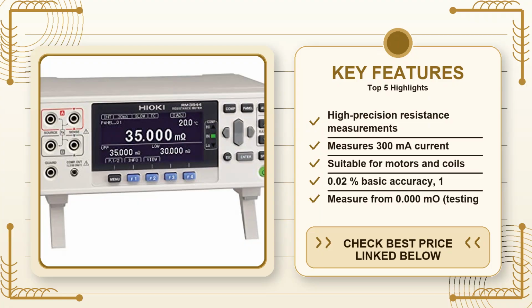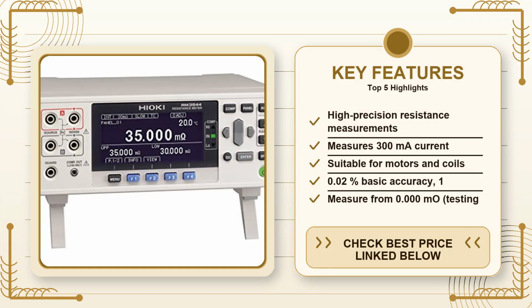When you talk about a portable resistance meter, the conversation is different than the usual let's grab any multimeter off the bench. Resistance work often happens in noisy environments, on the edge of a machine, or inside a vehicle where you can't just pull the power cord out and stare at a screen for minutes. The meter has to be precise, it has to be quick, and it has to give you confidence that a reading of 0.12 isn't a fluke caused by a bad lead or a stray magnetic field. That's the sweet spot the Hioki RM3544 tries to own.